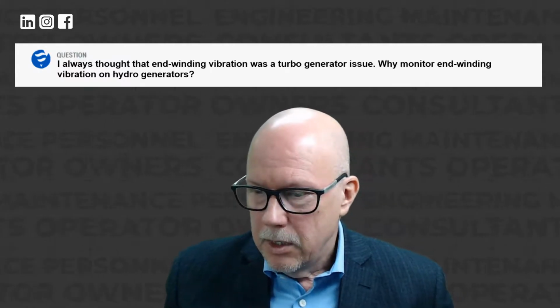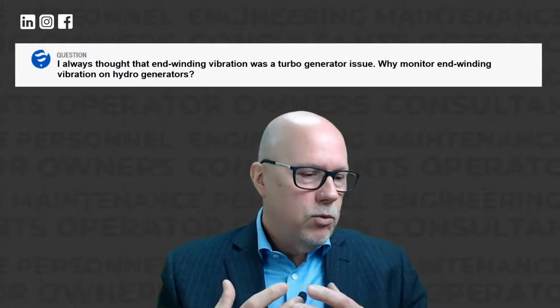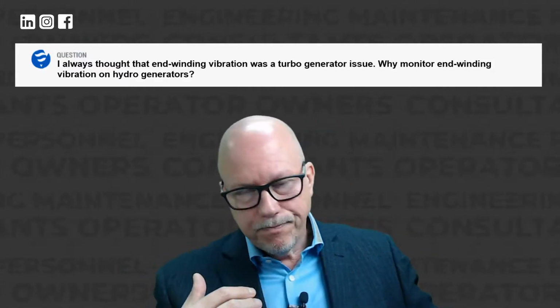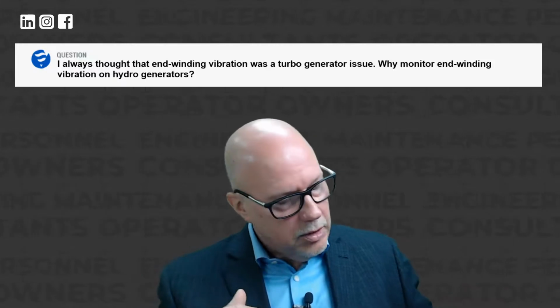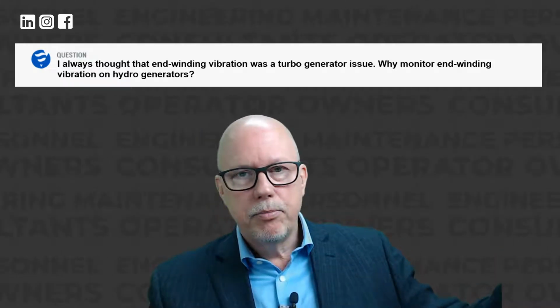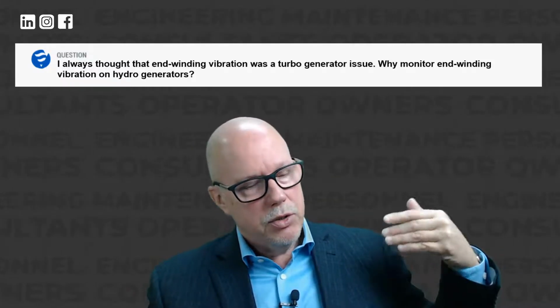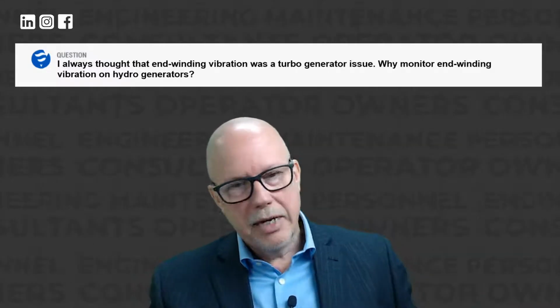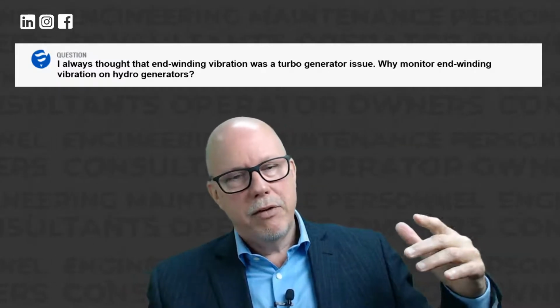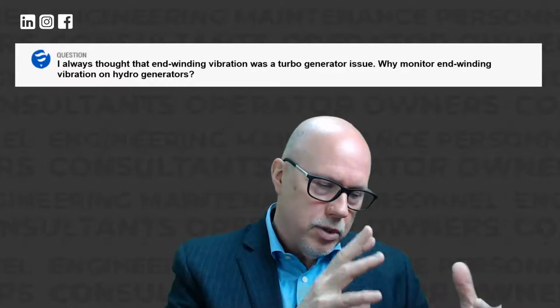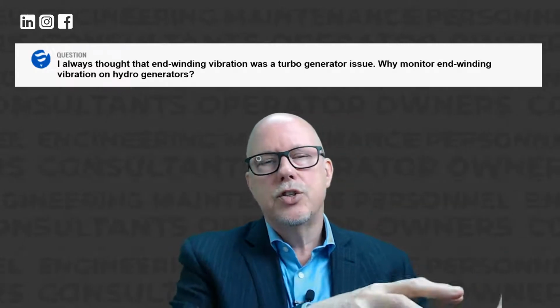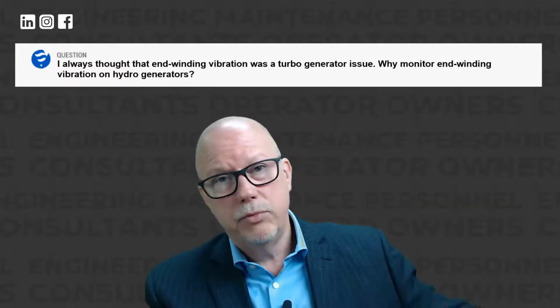Yeah. So the fact that the end windings on these units are very long, and since they're horizontal, well, gravity is actually pulling on them. And when you run the unit, you introduce electromagnetic forces. If you have resonance issues, there are all kinds of forces that will come into play that can cause issues on the end winding. Some of them are 2 meters long.